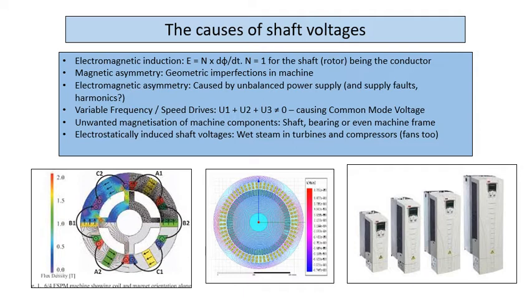And the reason why asymmetry is so important is if the machine is perfectly symmetrical and your voltage supply is perfect, those fields will just rotate and no one part of the field will penetrate the shaft anymore. So you will have no net flux linkage across the center line of the shaft. If you do, you have a shaft voltage. So the causes of that are ducts that are not uniform; each time the flux tries to pass those, it'll change. And then Stian's example was of a keyway in a shaft. And no machine is built perfectly, so they all have a shaft voltage. Let's go back. So there's your magnetic asymmetry.